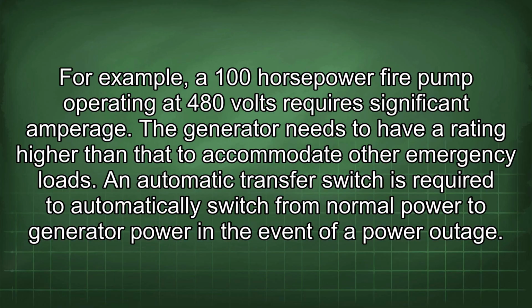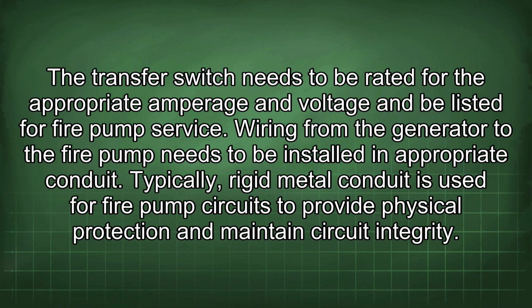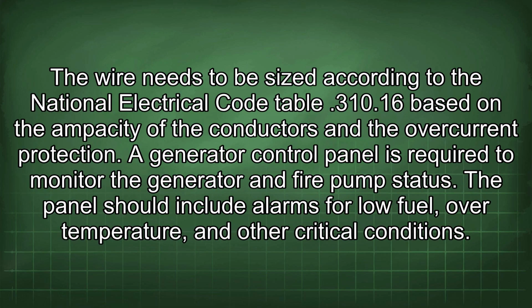An automatic transfer switch is required to automatically switch from normal power to generator power in the event of a power outage. The transfer switch needs to be rated for the appropriate amperage and voltage and be listed for fire pump service. Wiring from the generator to the fire pump needs to be installed in appropriate conduit. Typically, rigid metal conduit is used for fire pump circuits to provide physical protection and maintain circuit integrity. The wire needs to be sized according to the National Electrical Code Table 310.16 based on the ampacity of the conductors and the overcurrent protection.